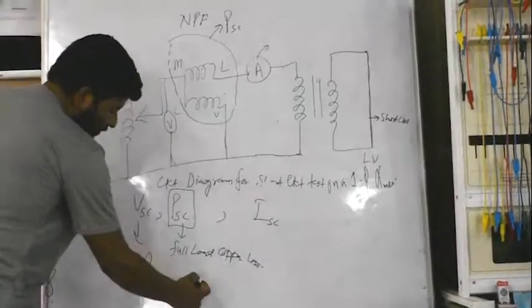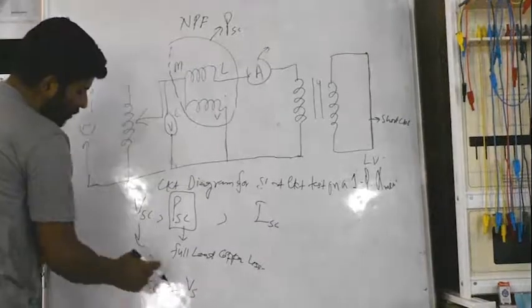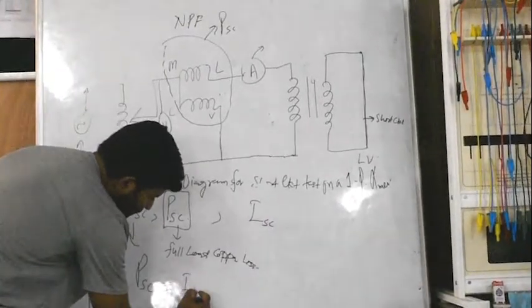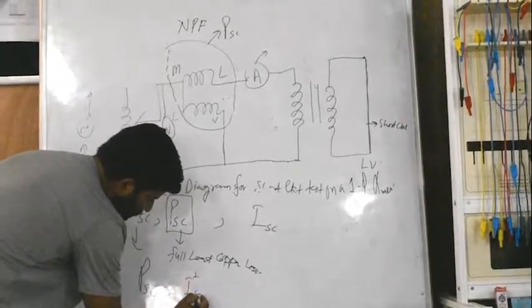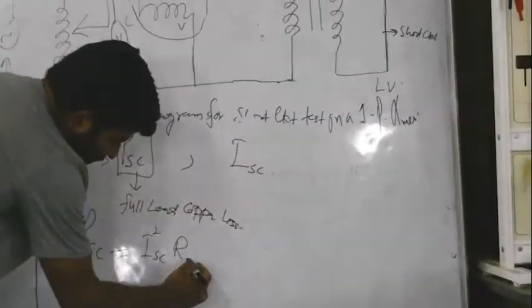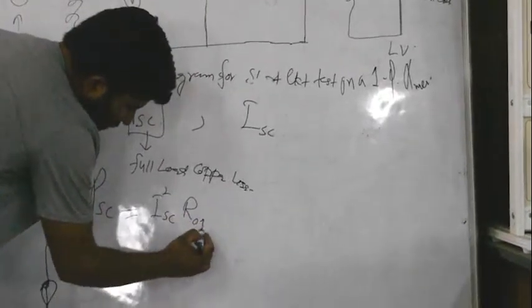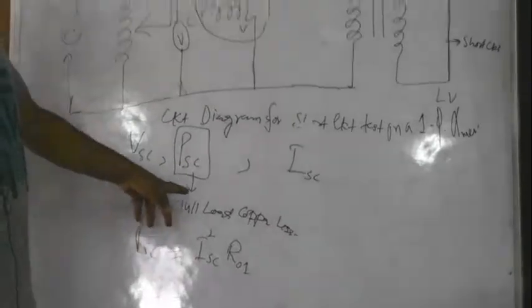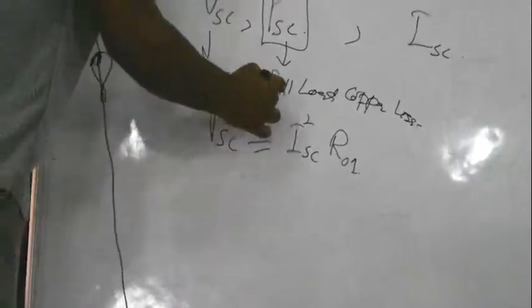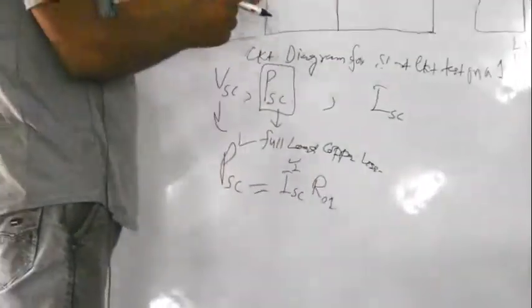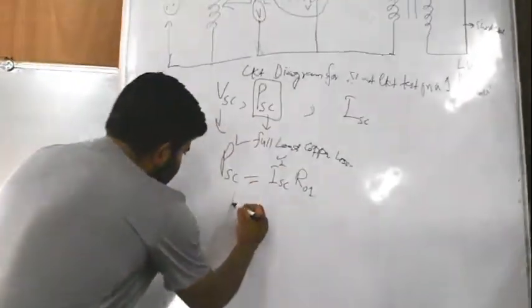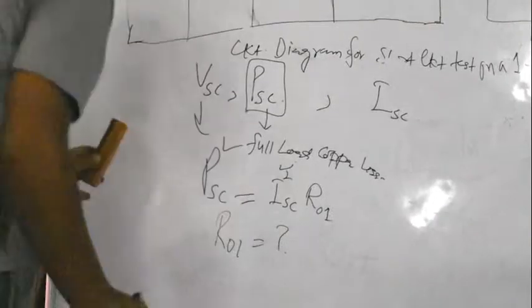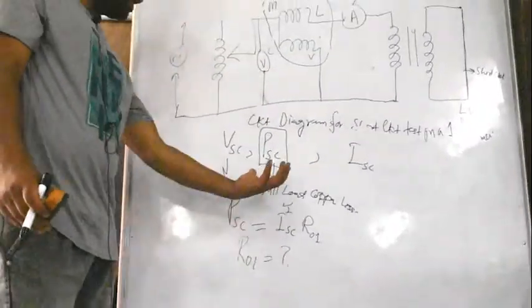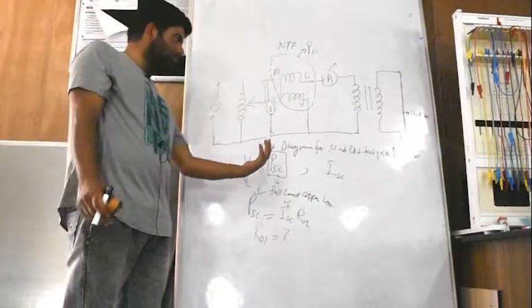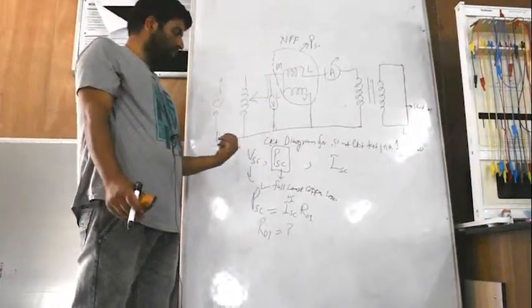To obtain the other equivalent circuit parameters, we can express the short circuit power as the product of I square SC into R01, where R01 is the resistance referred to the high voltage side. You know this quantity from the wattmeter readings, and from that you can calculate R01. So you obtain the equivalent resistance as referred to the high voltage side, the side from which you are doing the experiment, right?